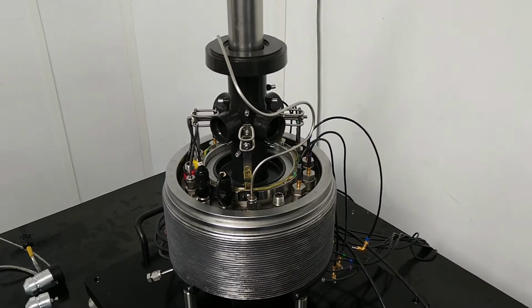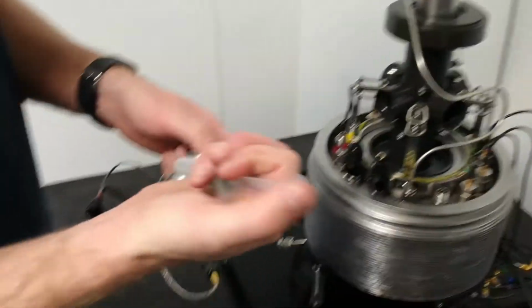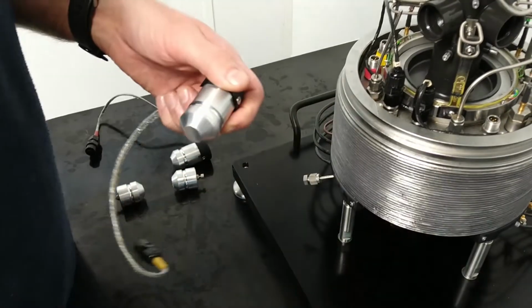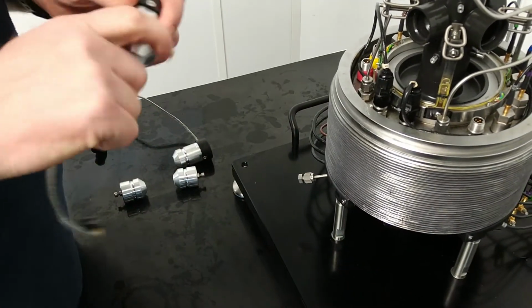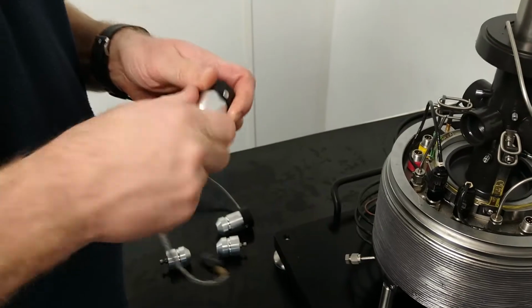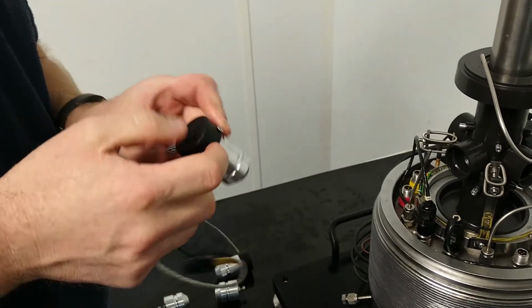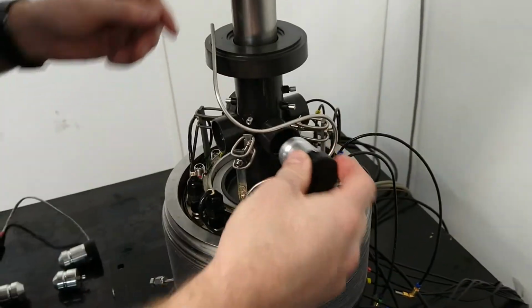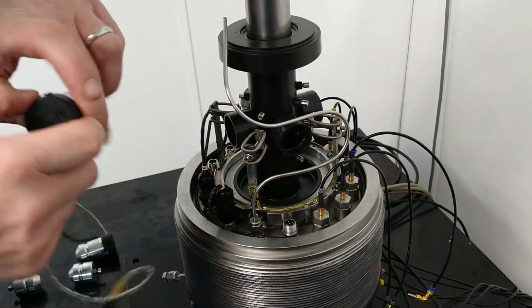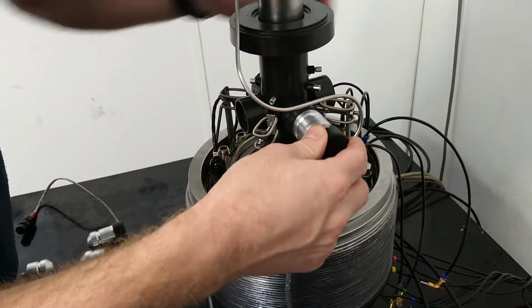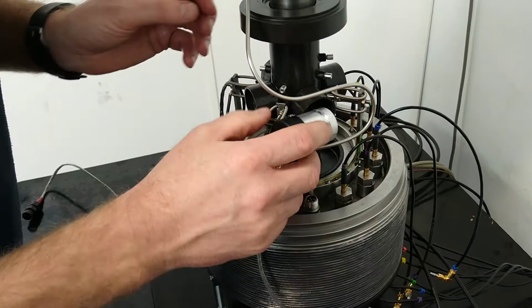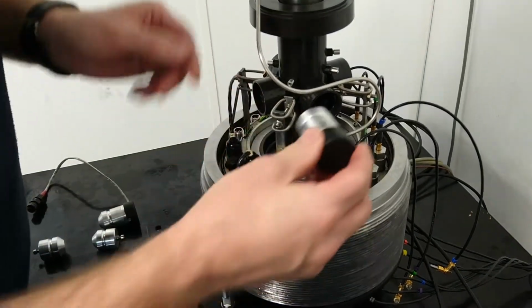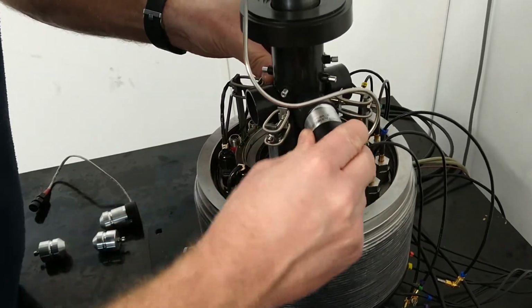To fit the horizontal acoustic velocity transducers, apply silicone grease around the sealing face and insert into a predetermined location on the membrane. The AV holes on the membrane have a sealing ring which will locate into the corresponding groove on the transducer tip. When fitted correctly, you will feel a click as the seal locates into this groove.